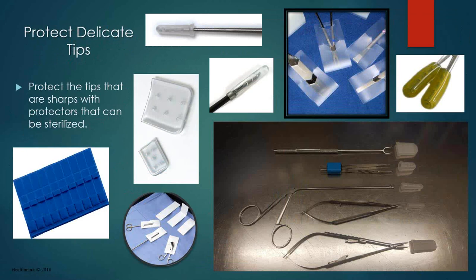When evaluating new tip protector selections, make sure you include the OR so they know what types are being looked at, not just vented versus non-vented, but also the color. The color is very important at times. I've been in facilities where the OR wasn't told they switched from a colored to a clear protector, which is fine, but because they weren't told, they dropped or left the tip protector inside the instrument, and it fell into the patient. Luckily, they were able to retrieve it. But again, it's very important to let them know.